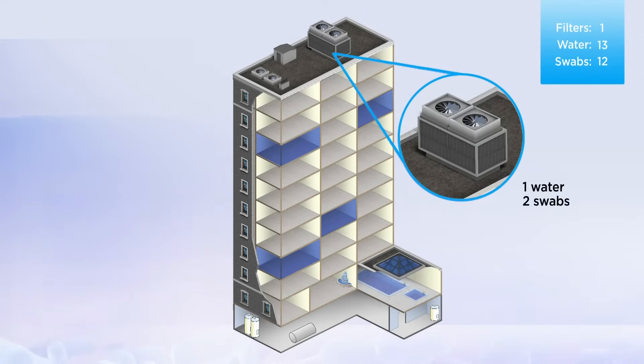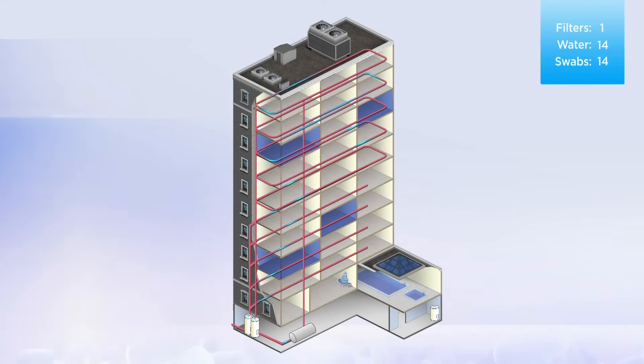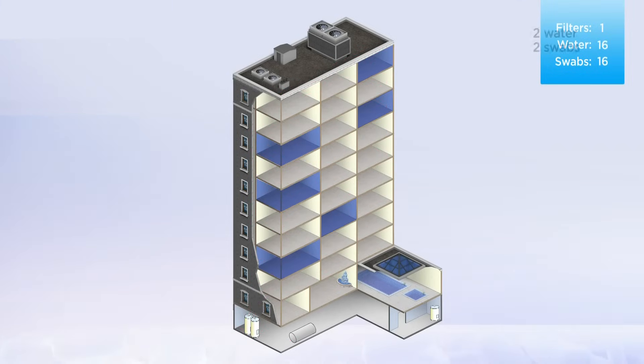Since there is a cooling tower on the roof, all case patients could have had exposure to it, so it should be sampled as well. To ensure representative sampling of the premise plumbing, you should also take some samples that are close to and far from the hot water heaters on the upper floors. In this example, we'd sample on the 6th and 10th floors.